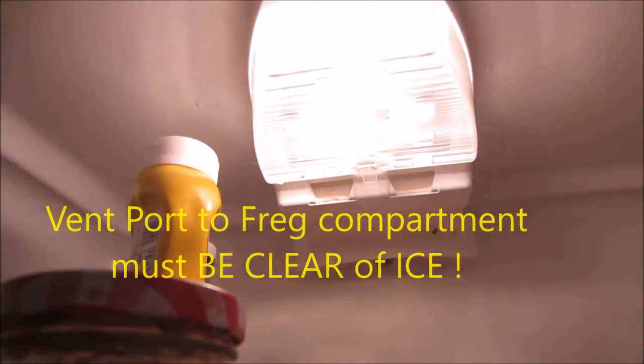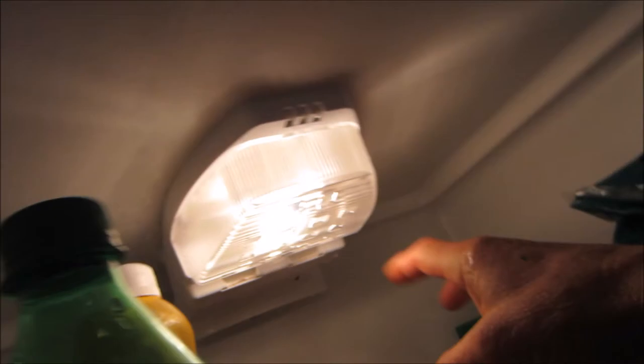That port is plugged up right there. You can see this drain may be plugged up — little bitty drain. The ice built up back there. May have to take that whole thing off and clean that drain out.